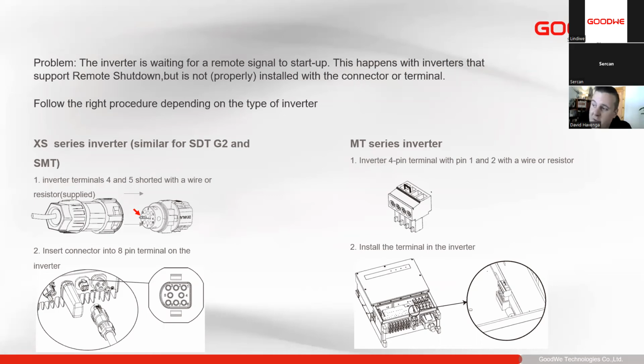So with all these different ones, like the XS, the SDT G2, the SMT, the ET Plus, all come with a proprietary little plug in the box. Some of them may be round, some of them may be square. That plug already has a wire bridge in it, and it simply needs to be installed in the inverter.